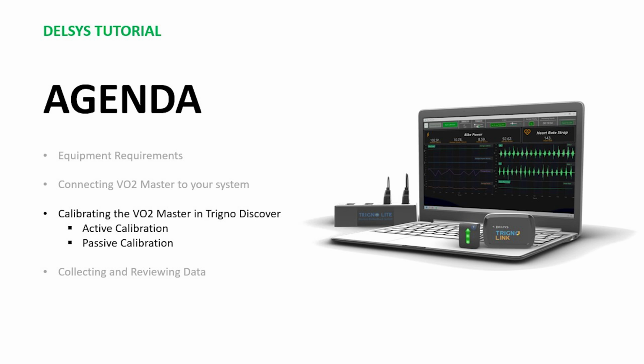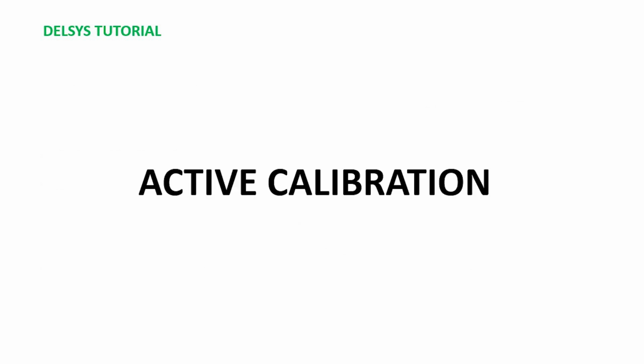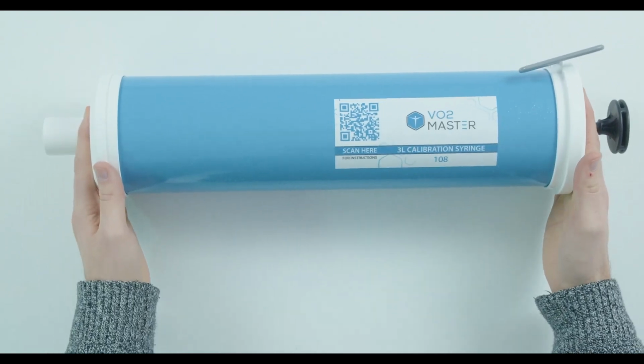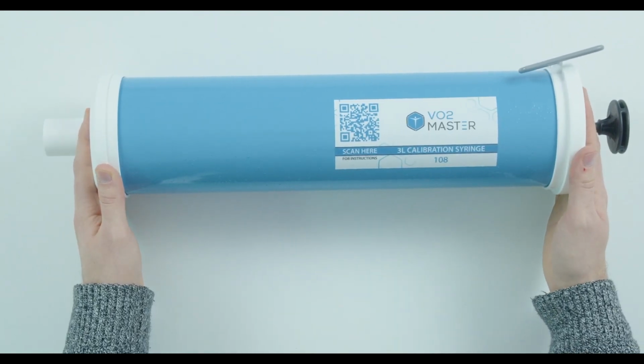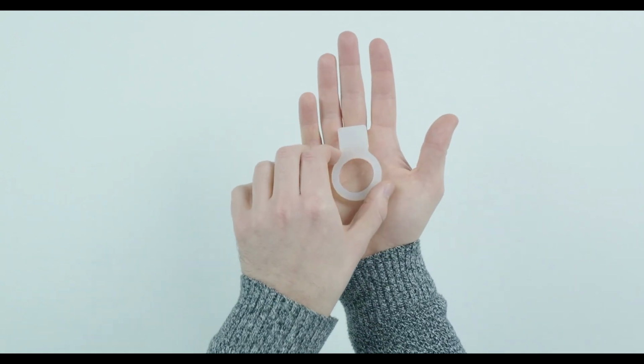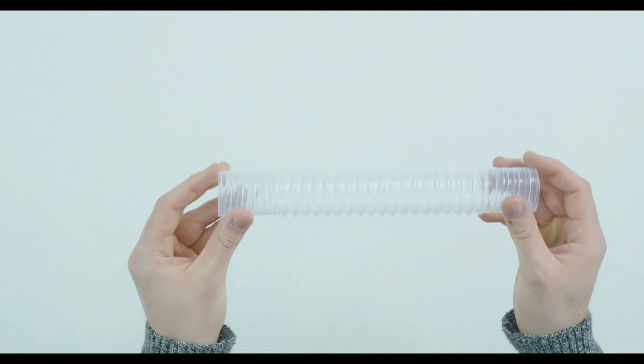This section will demonstrate the two techniques to calibrate your VO2 Master: active calibration and passive calibration. We will begin with active calibration. To perform an active calibration, you will need a 3-liter calibration syringe, a calibration syringe adapter, a calibration syringe adapter silicone seal, a 30-centimeter flexible tube.